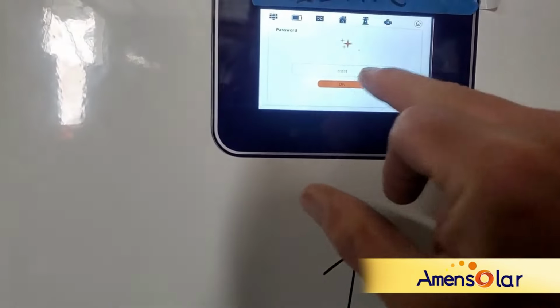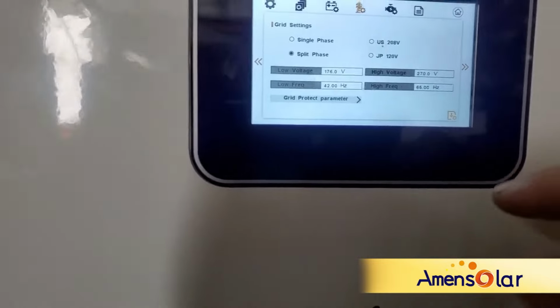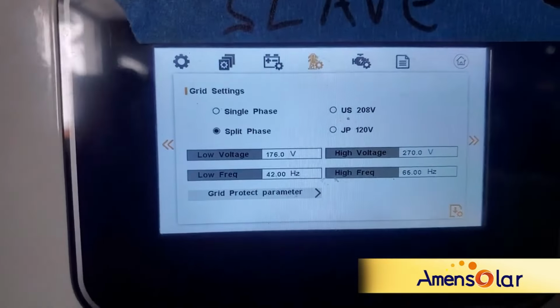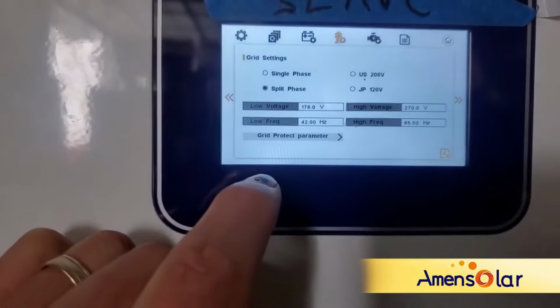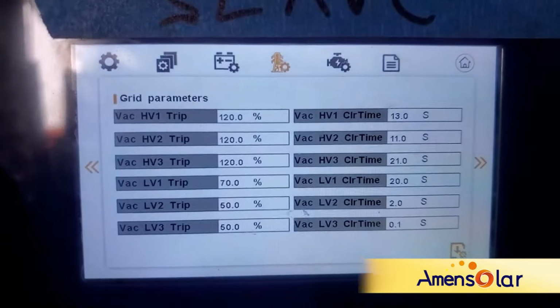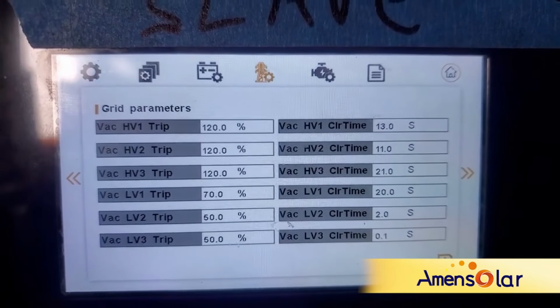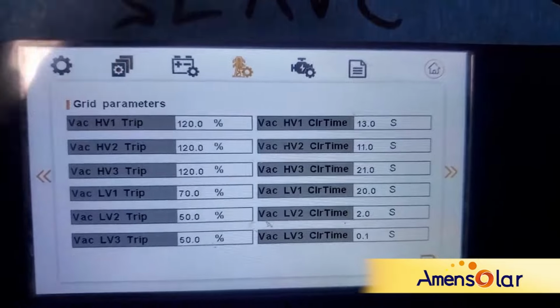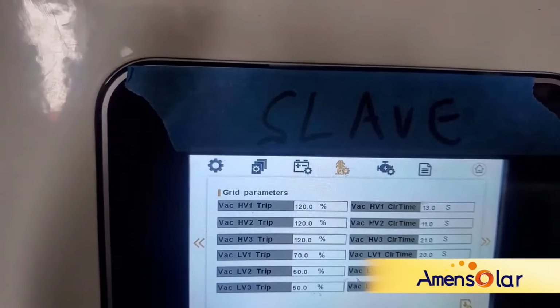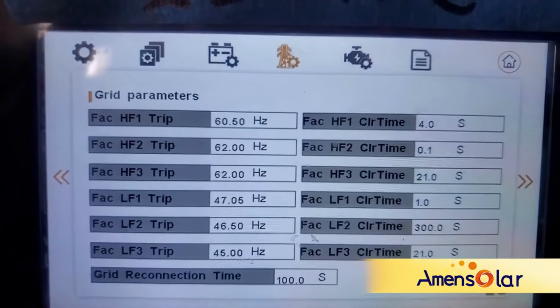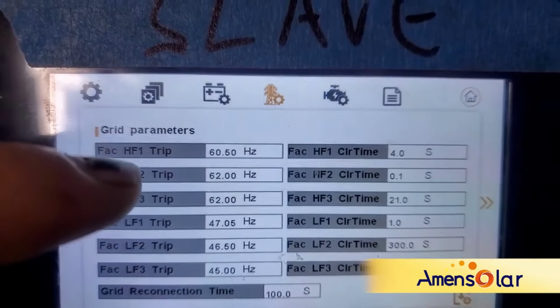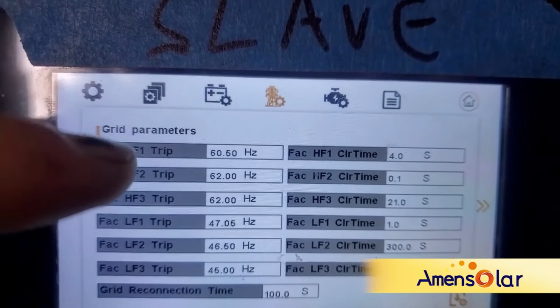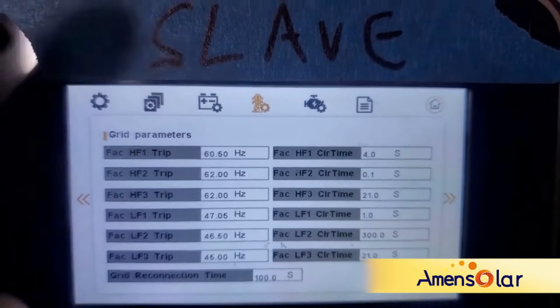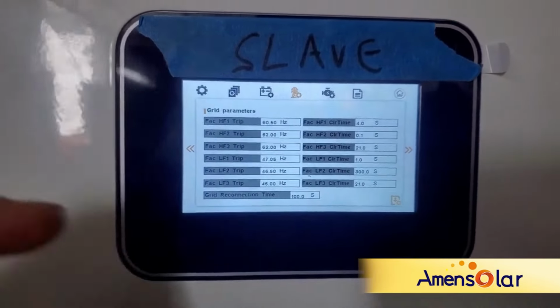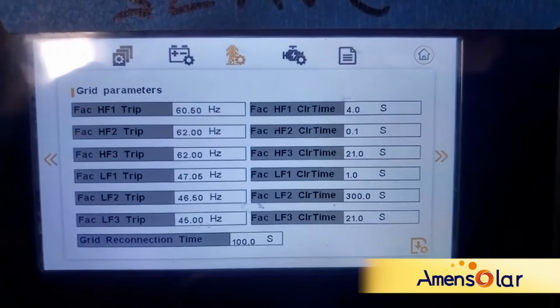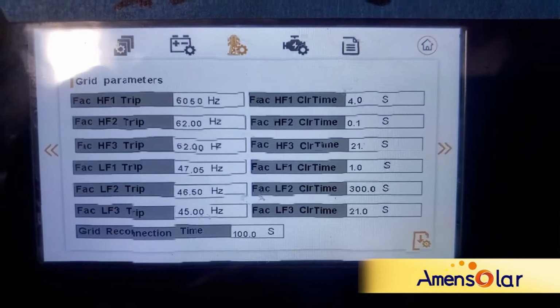You could set, for example, in the parameters, you can set on the grid over there. And this is split phase right now, where the high voltage is, where the low voltage is. You can click grid protect parameters. So if the voltage goes too high, if you're feeding back too hard or something in your system, it can shut down. Then also you can go via frequency as well. So the inverter indoors, if the battery is full, it will just adjust the frequency up to 60.5 hertz, and that will stop this set of inverters feeding back power to the one indoors. And pretty awesome.